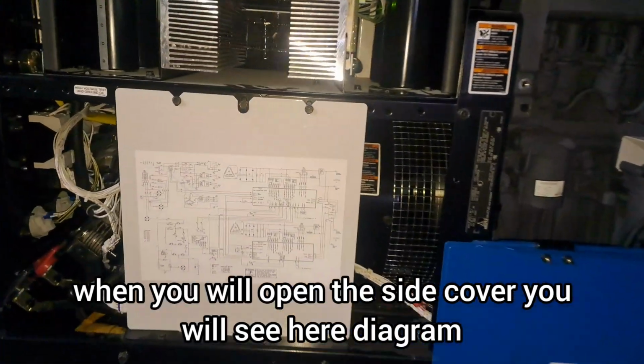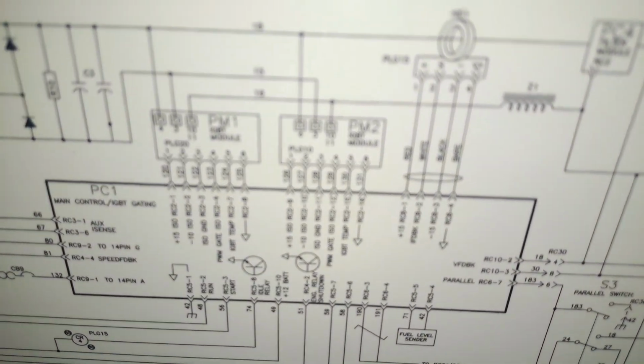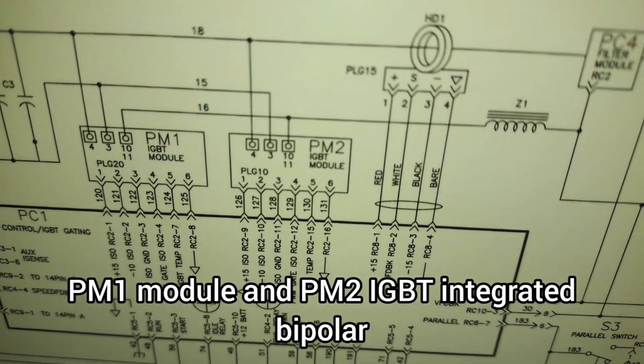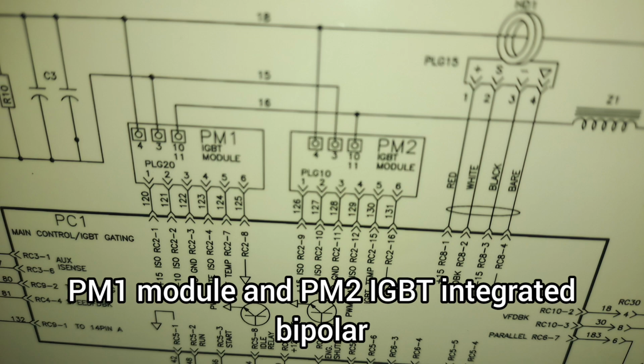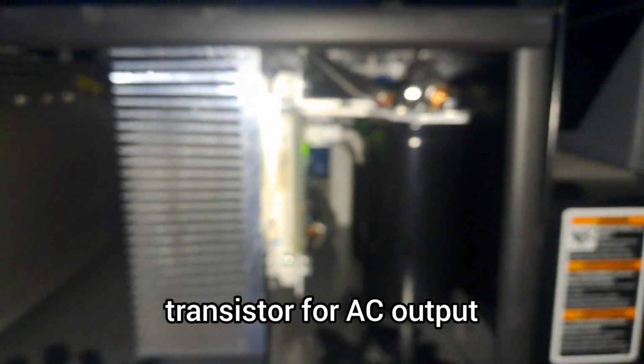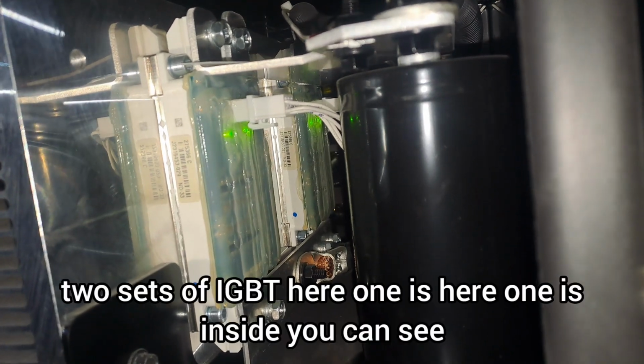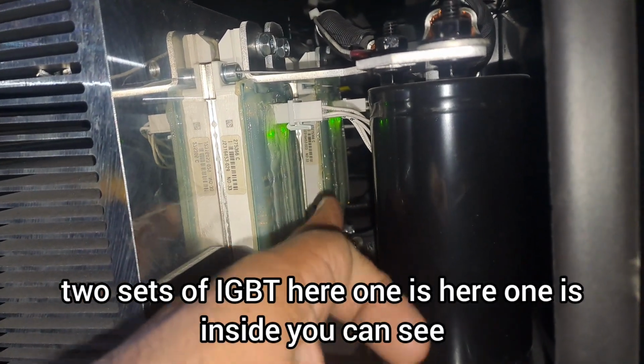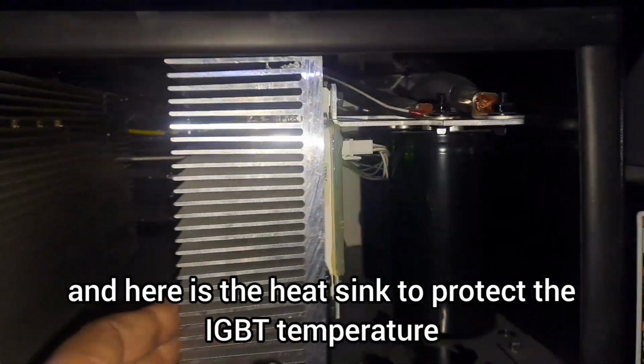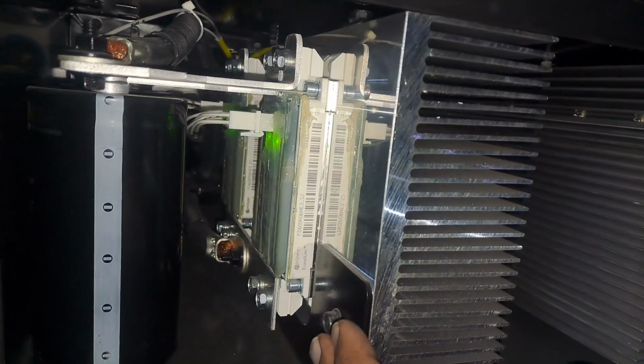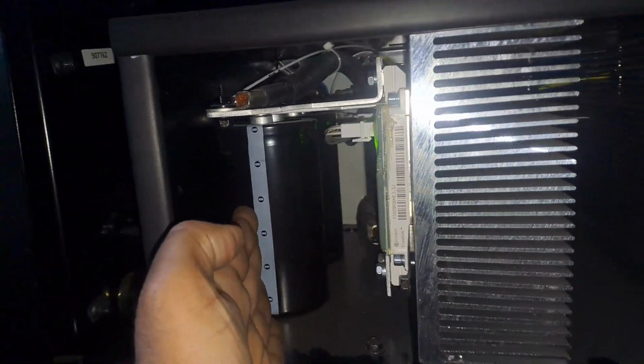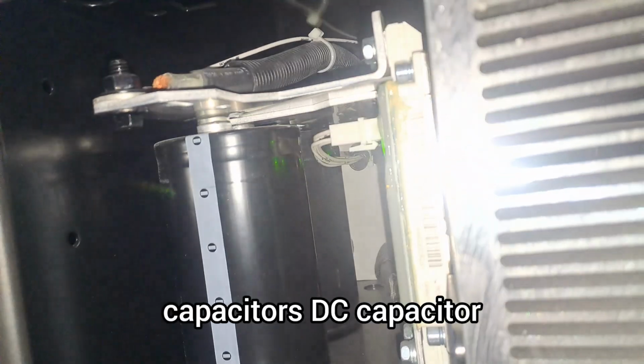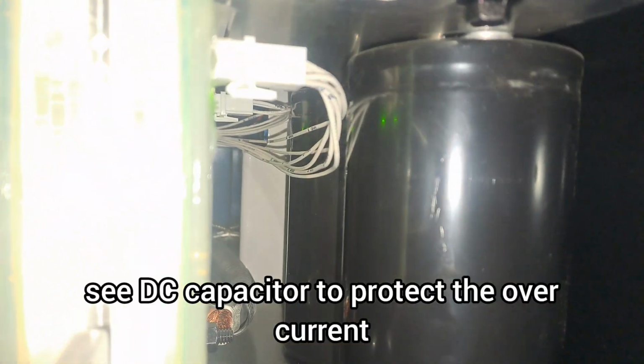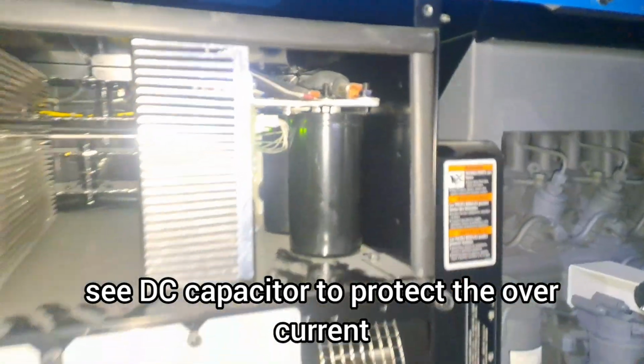When you open the side cover, you will see the diagram here, and you see the PM1 module and PM2 IGBT, insulated gate bipolar transistor, for AC output. You see here 2 sets of IGBT. One is here, one is inside, you can see, having a green light. And here is the heat sink to protect the IGBT temperature. This side also has 2 IGBTs and 2 DC capacitors, see, DC capacitors to protect against overcurrent.